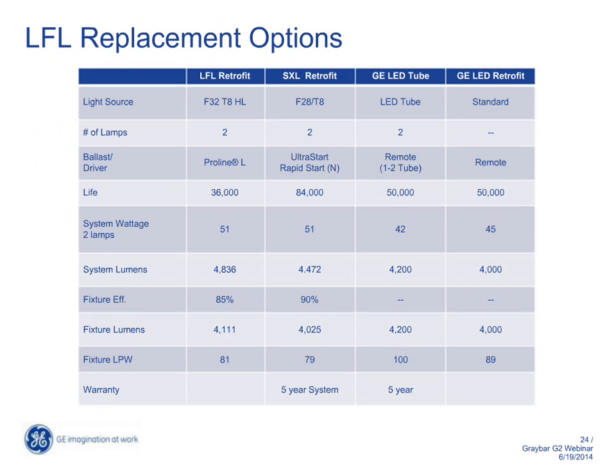As you start looking at some of the numbers, hopefully if you could put that up to full screen, you can read them a bit better. I think what this chart shows is how far LEDs have come. It hasn't been that long ago, about 2 years ago, that the Department of Energy had a report where they said that LED tubes weren't quite ready for prime time. This shows that LED tubes clearly are. A GE LED tube with remote driver, fixture lumens per watt is about 100. A GE LED retrofit kit is going to be somewhere around 89 or 90. And how does that compare with a linear fluorescent?